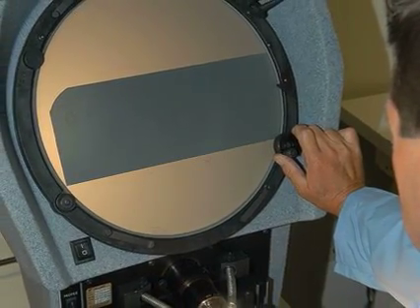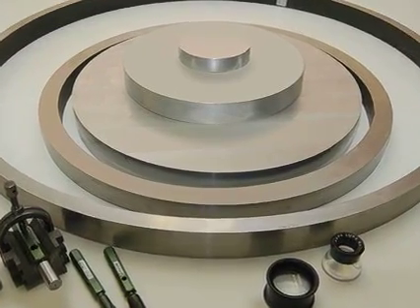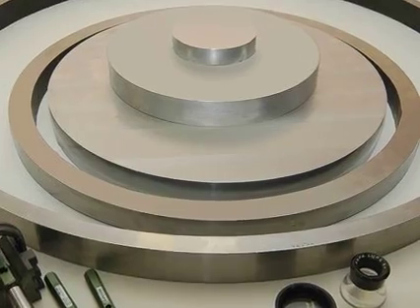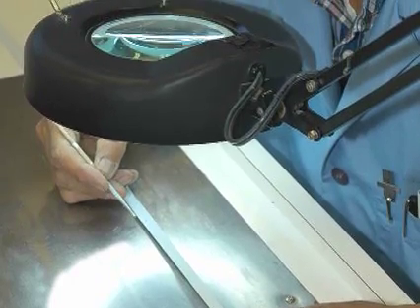Pi tape gauges are calibrated at 68 degrees Fahrenheit. These O-ring specialty tapes read to 0.03 millimeters with an accuracy of 0.09 millimeters on standard ranges up to 900 millimeters.